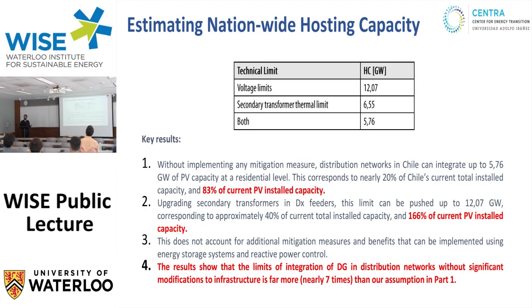We used that to extrapolate the hosting capacity of the whole country. What we observe is that if we only care about voltage limits, we can integrate up to 12 gigawatts of peak solar generation—almost 7 times what we assumed previously, where the peak was at most 1.8 gigawatts. If we also consider secondary transformer thermal limits, the limit goes down to 6.55 gigawatts.